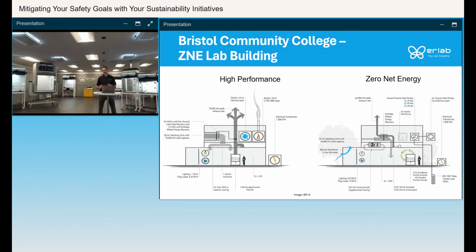So they saw that ventilation was the biggest energy user in the building. So they thought if they could decouple conditioning from ventilation, they'd be able to have a significant energy savings. They also thought if we could have an air quality monitoring system, we can probably keep all the labs at 4 air changes per hour occupied, 2 air changes unoccupied.